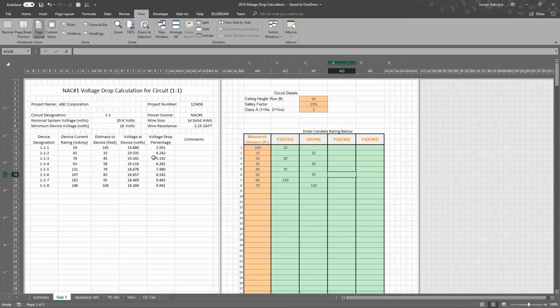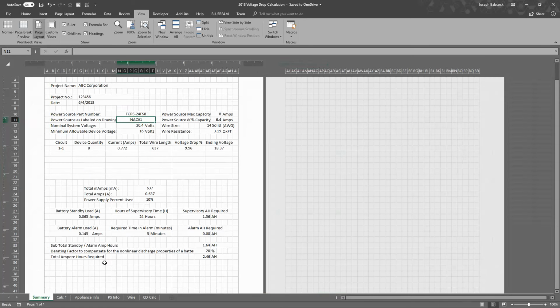So entering in just candela and just wire length, without having to think about adding wire length or creating any kind of additional safety factors, I think the spreadsheet does that for us and covers our bases. So that brings me to, let's do the batteries.